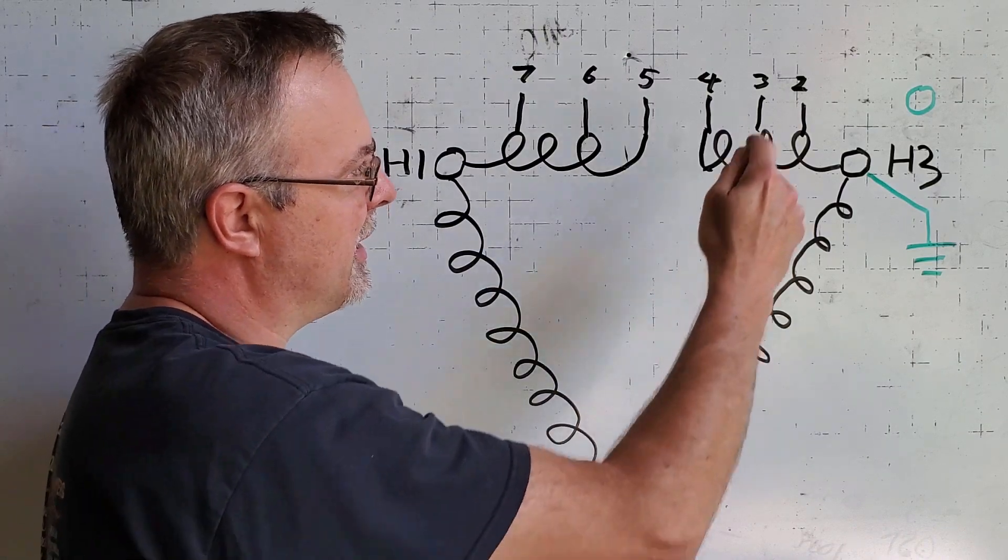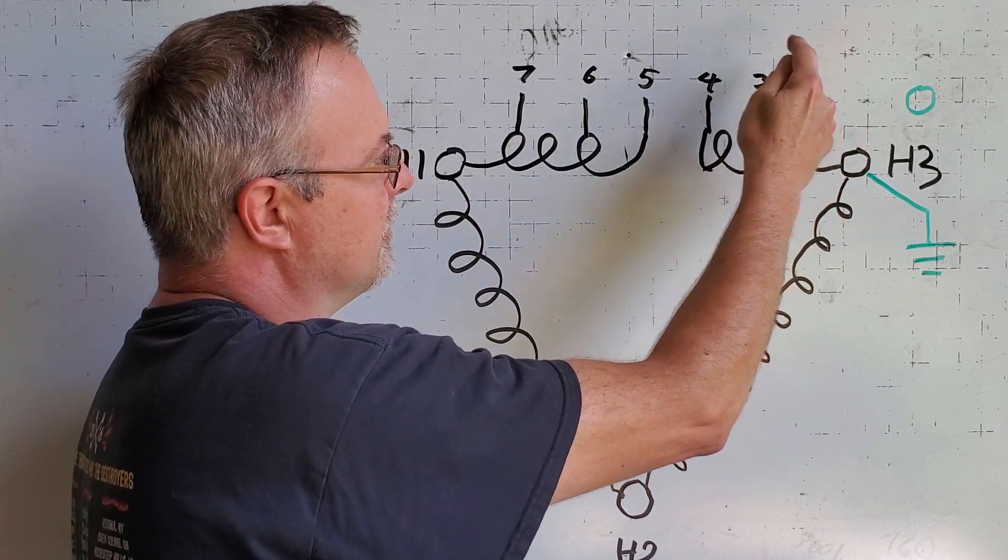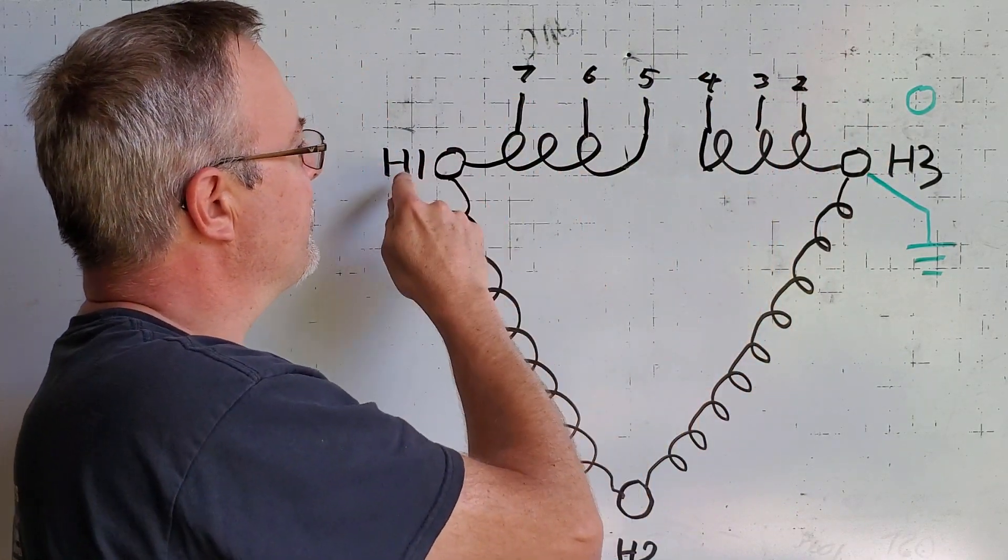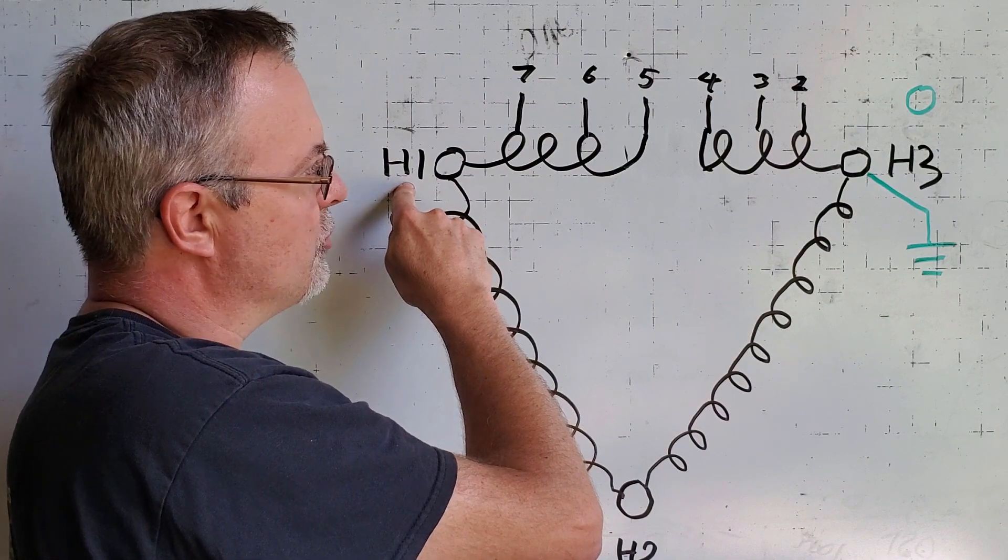What we're going to do is we're going to apply the 120 volts to the low voltage side and I'm going to call out the voltages and we're going to write them down here from zero on up through to the high leg of H1. So let's get over to the transformer and take our measurements.